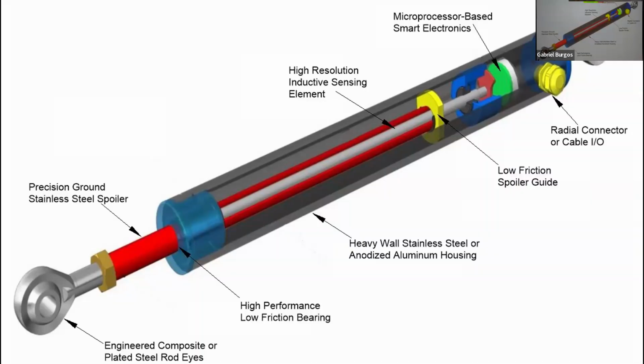If you're only into the coil a little bit, you have relatively small eddy currents. As you push it in more, you get more and more eddy currents. Those eddy currents establish counter fields to the existing RF field of that coil.